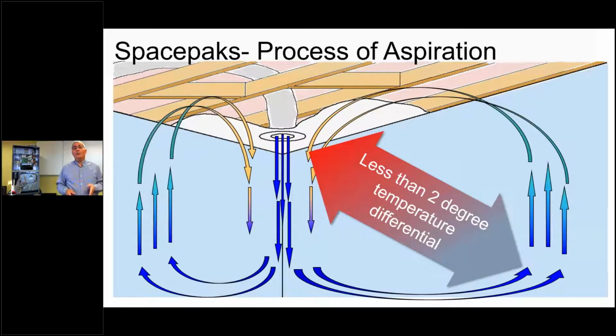So you want to be aware when you're looking at a room or looking at a home and putting a SpacePak system in, where do I put those outlets? Because that column of air is a pretty strong column of air. So I don't want to put it where I'm going to be blowing directly on someone or on something. If the big tall plant is flapping around in the room, that's not a good place for the outlet, or we have to move the plant. But if I'm blowing it right on top of Mr. Smith where he sits in his lazy boy, probably not a good idea. So we try to get our outlets as best as we can in the corners of the room where nobody will be standing.